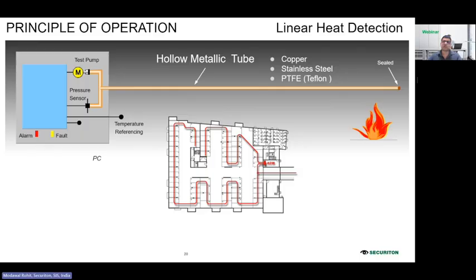And when these tubes are exposed to heat, in terms of fire, overheating, or radiant heat, the air inside the tube expands, and this expansion creates a pressure rise inside the tube, which the detector's pressure sensor continuously monitors.